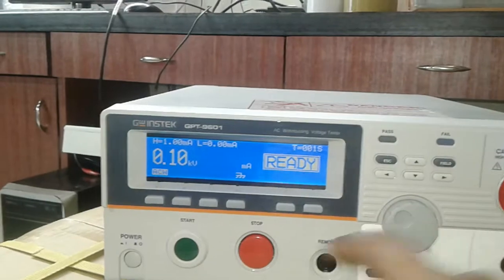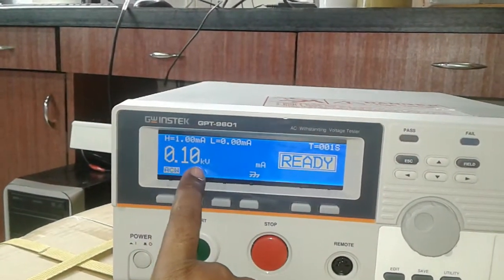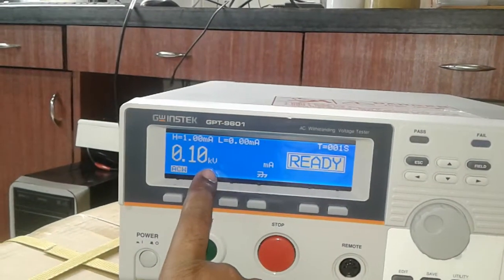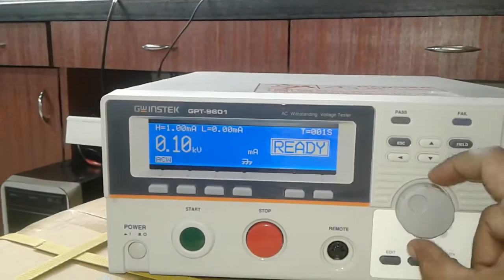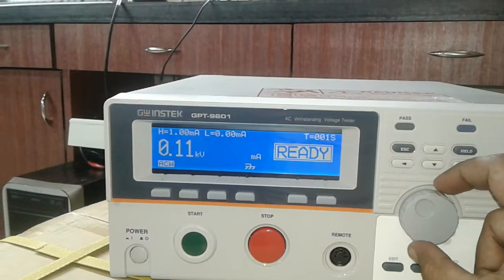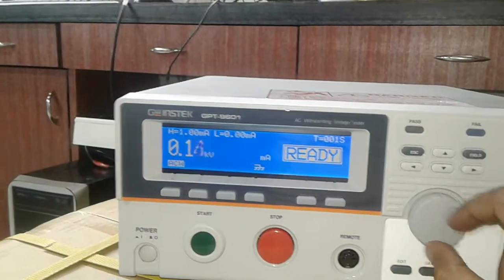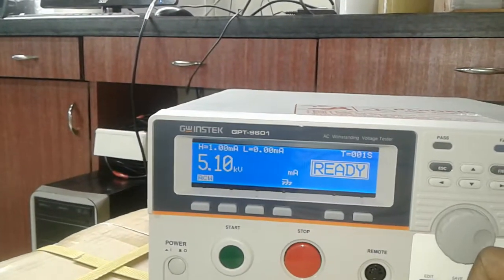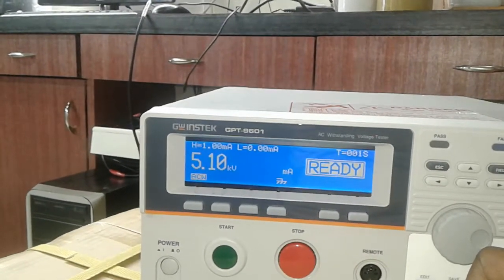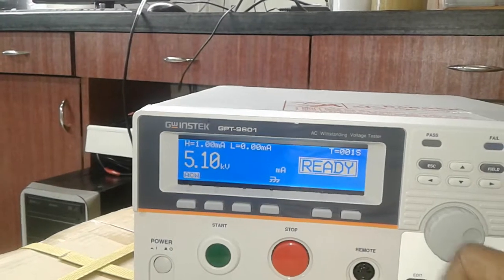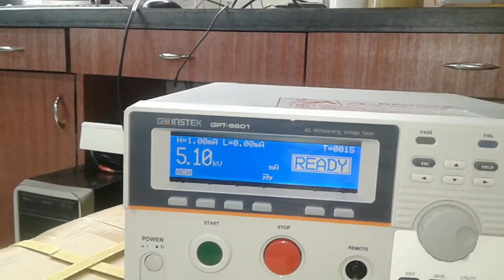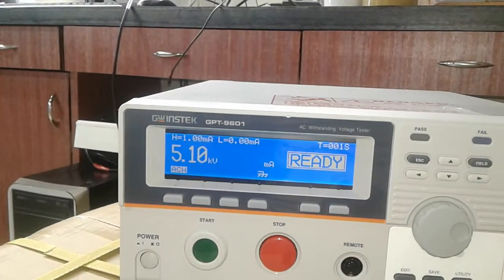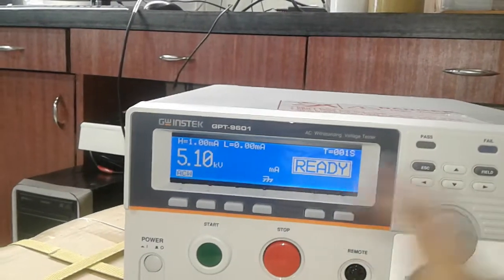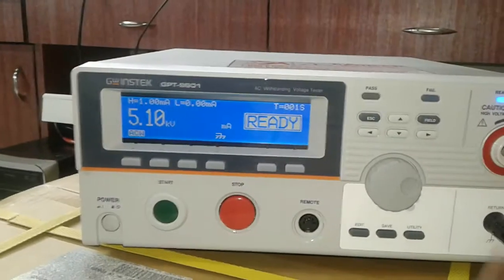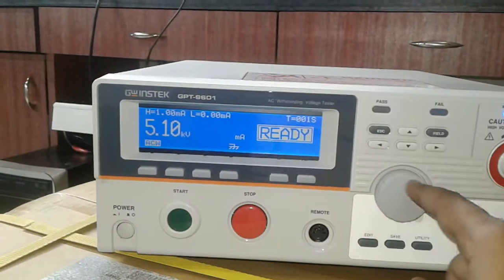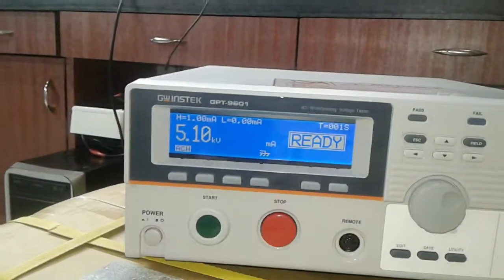Okay, so the minimum voltage is 0.1 kV. Okay, so 100 volts minimum. 10 volts per division is the resolution. Maximum is 5.10 kV. Okay, and the highest leakage current is 20 milliampere. Actually it is a 100 VA capacity HV tester. So very simple to operate.